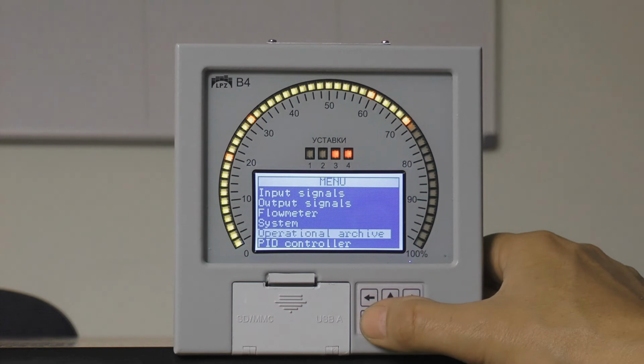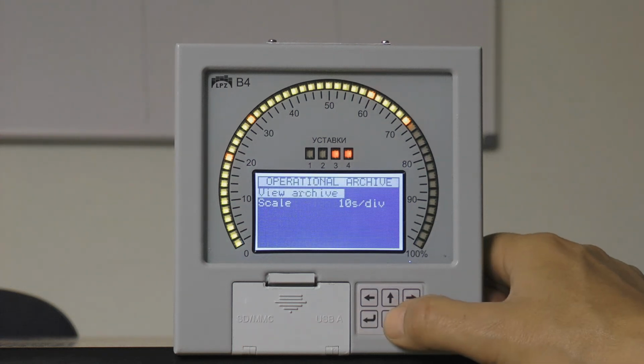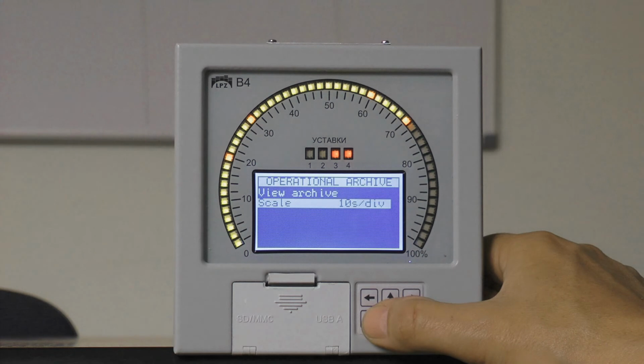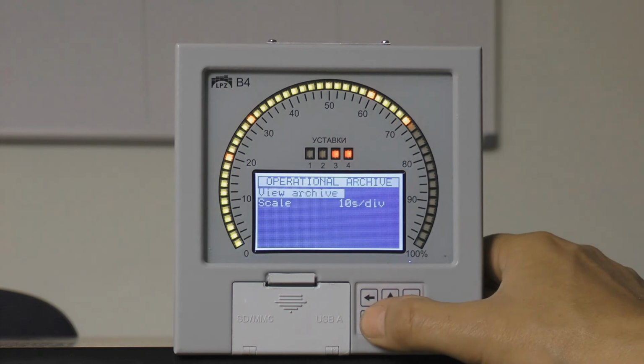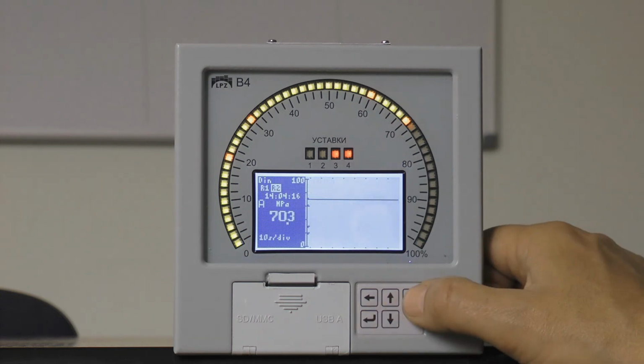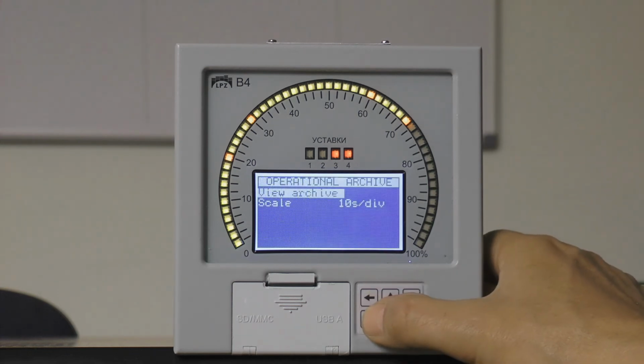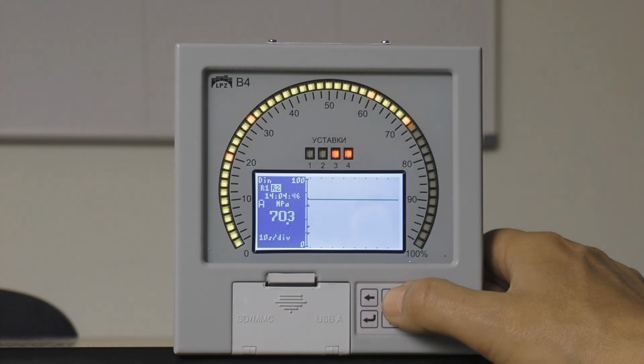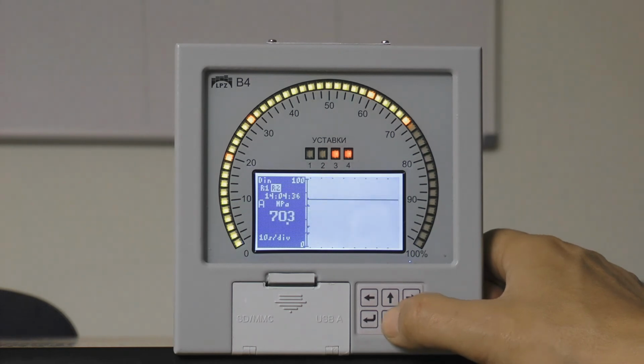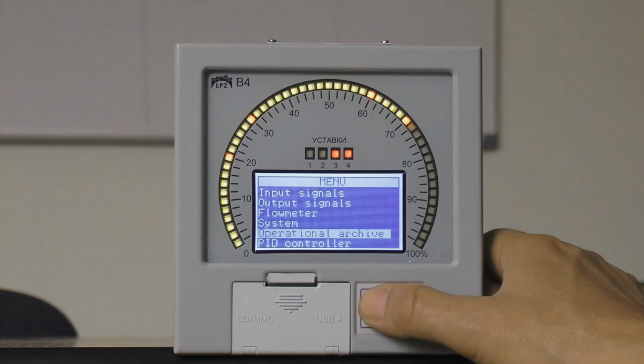The next setting I want to show is operational archive. Operational archive is a part of the archive which is available for displaying on the instrument's screen. Operational archive is displayed as a chart in a chosen scale. As you could see, the scale is 10 seconds per division now. Alright, to see the archive, we have to go to View Archive. The size of archive is 64 values of its scale. In our case, the scale is 10 seconds, so the size of the archive is 640 seconds. If the scale is 1 hour per division, it will be 64 hours.